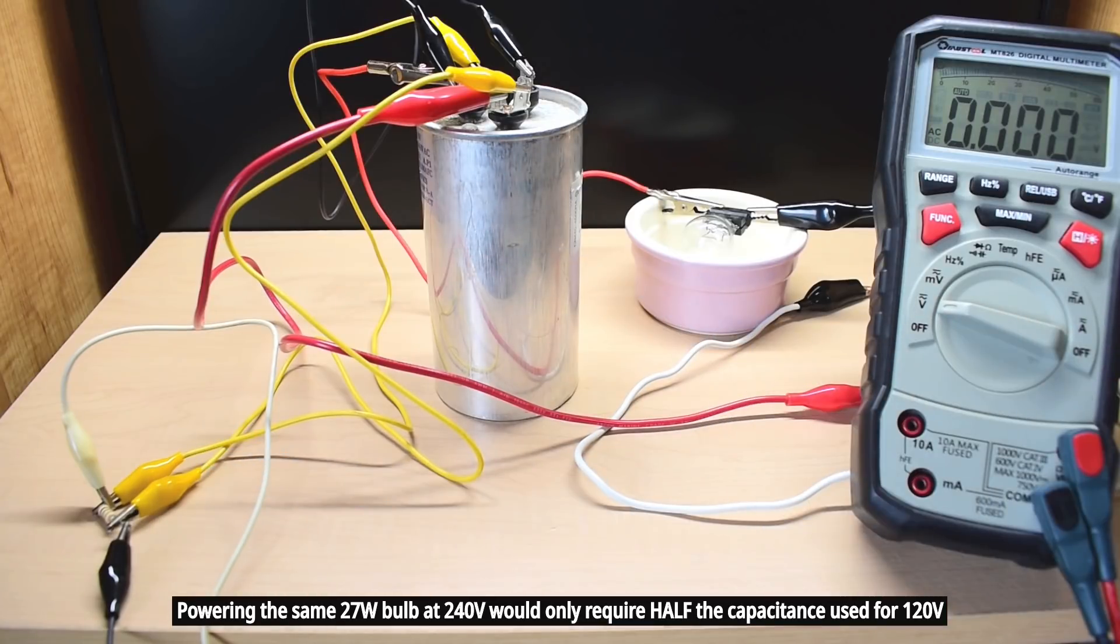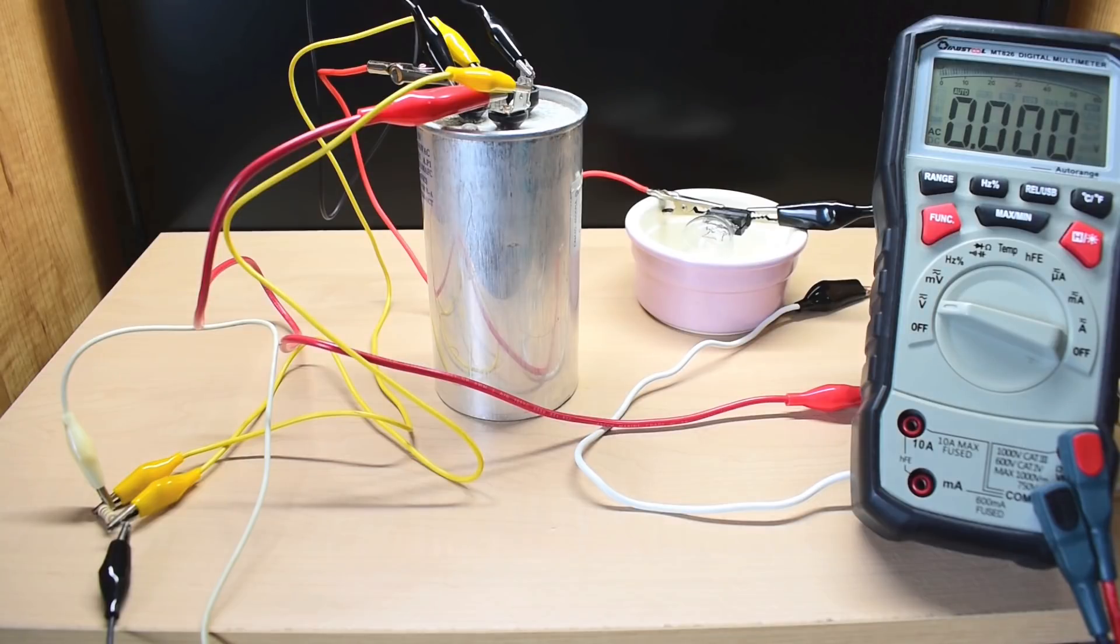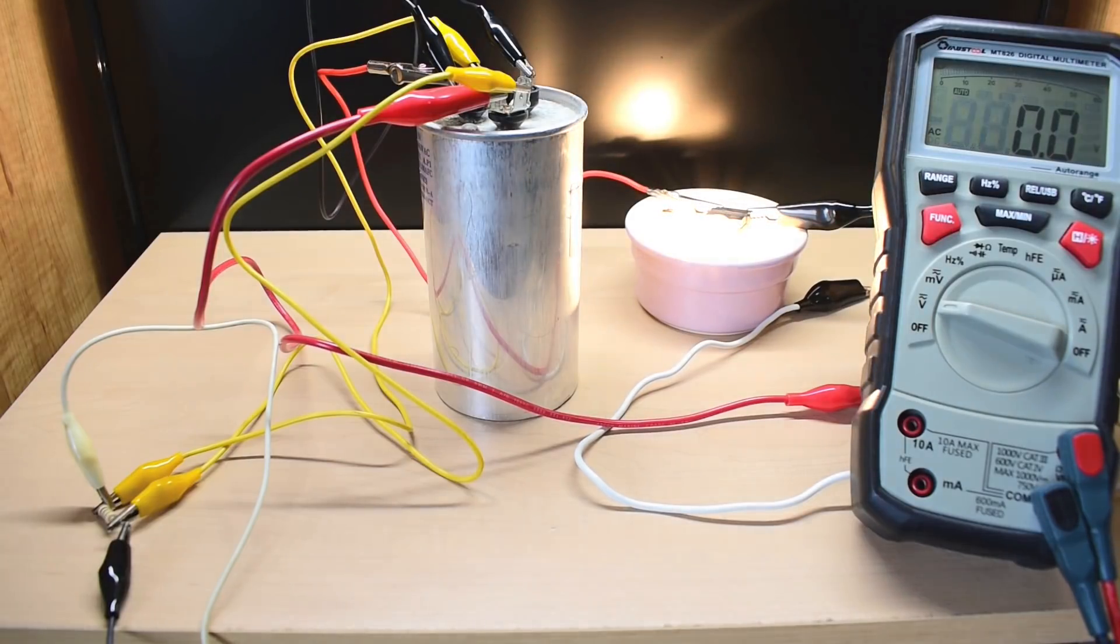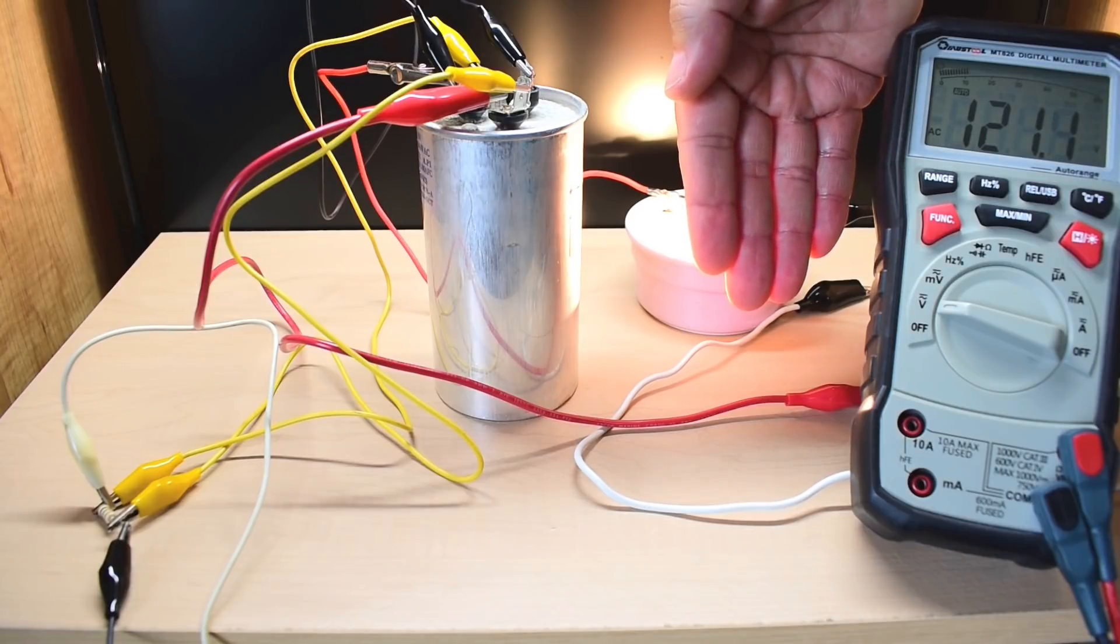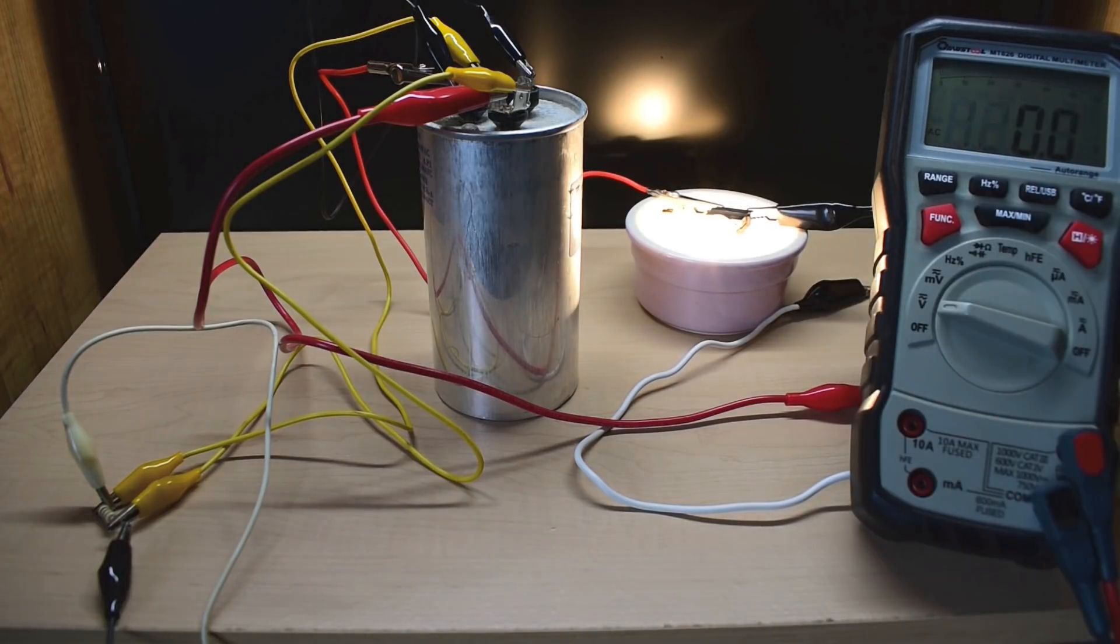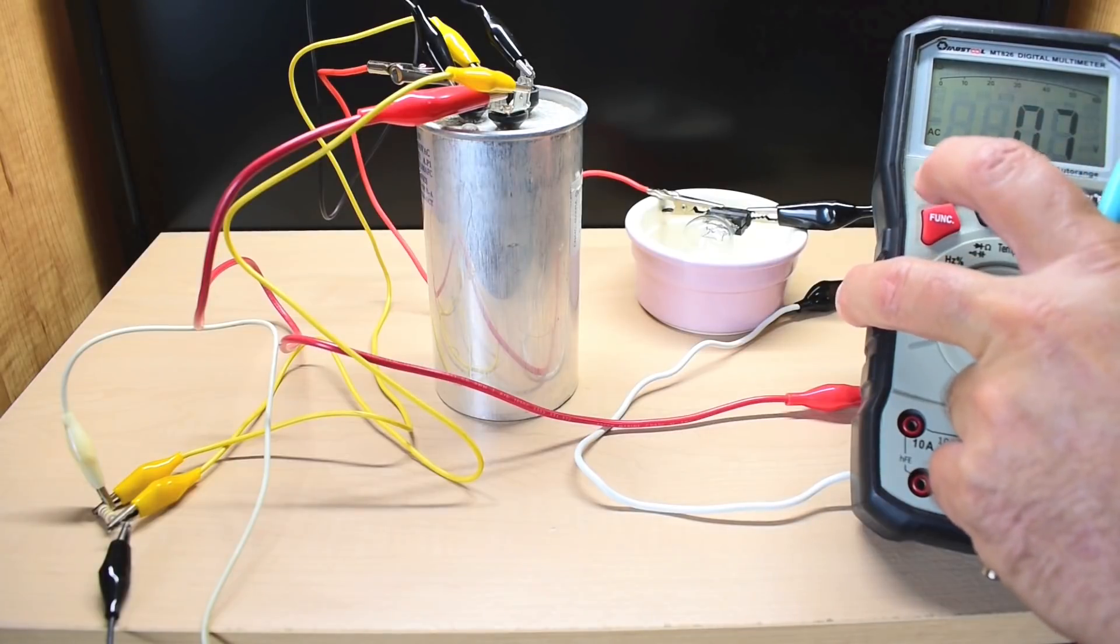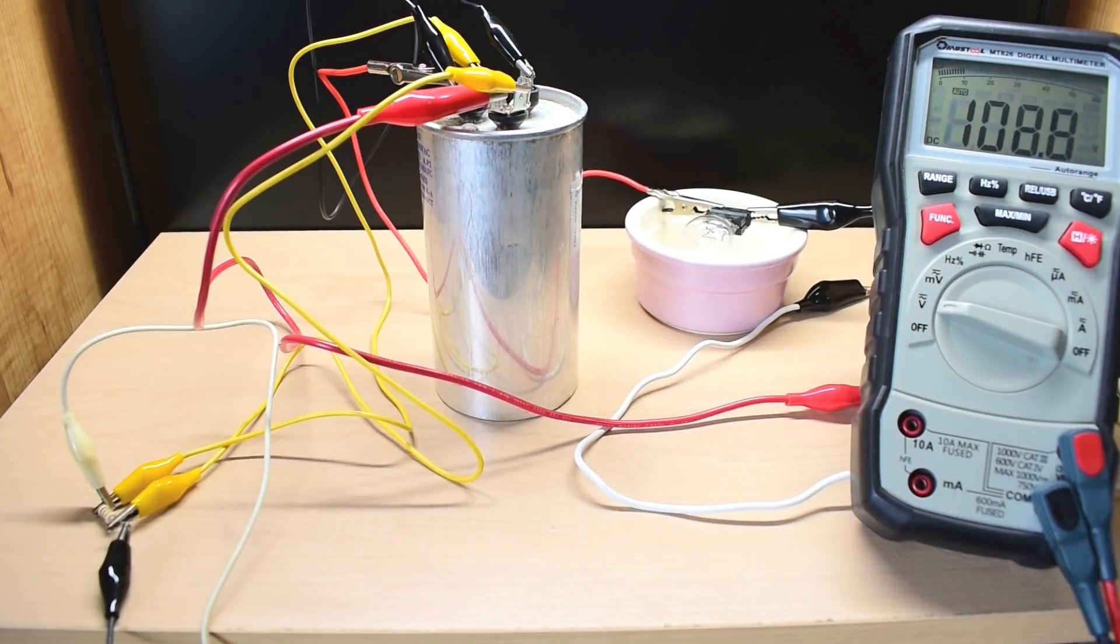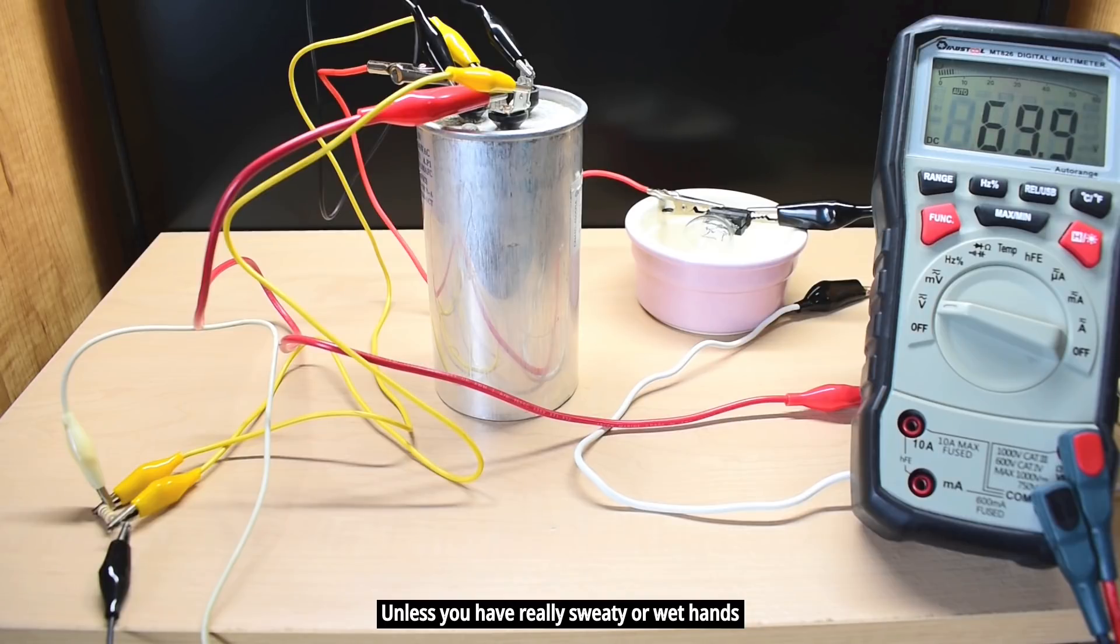All right, just to show you how this resistor bleeds off the charge when power is disconnected, I'm going to plug this back in. All right, you can see line voltage is at 121. Now when I disconnect this, I'm going to switch this to DC. You can see it's bleeding off that charge. And it does it fairly quickly for the amount of capacitance that I'm using. When it gets below 50, it's pretty safe to touch. It takes about 20 to 30 seconds to get it down low enough.